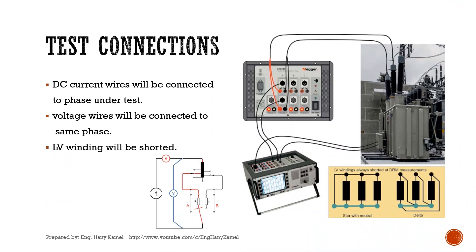Test connections: DC current wires will be connected to the phase under test, voltage wires will be connected to the same phase, and the LV winding will be shorted.